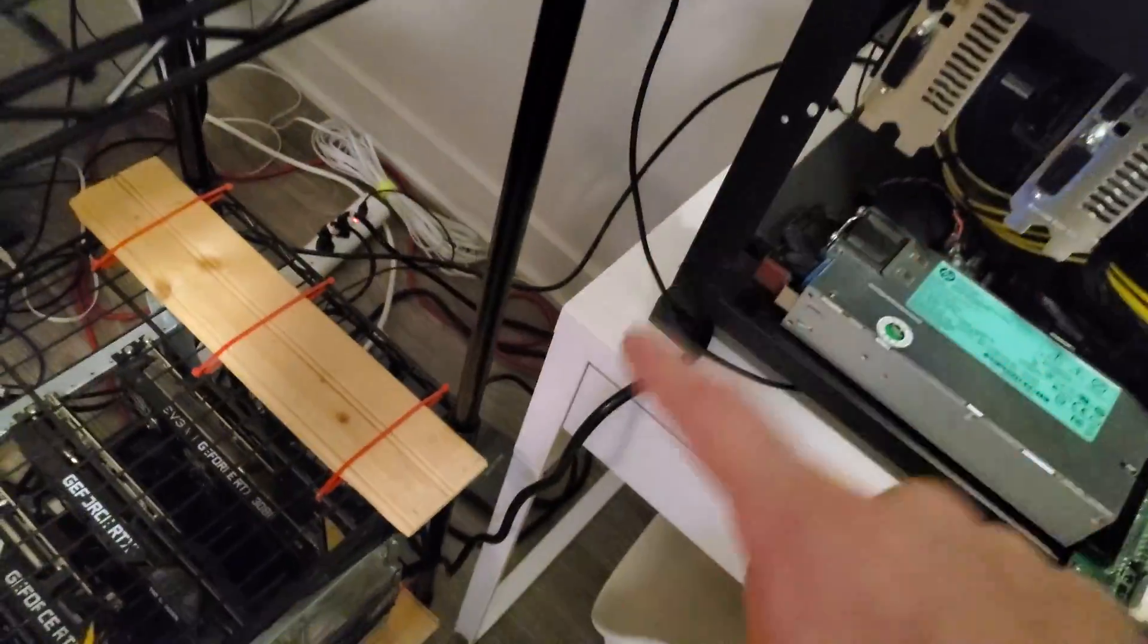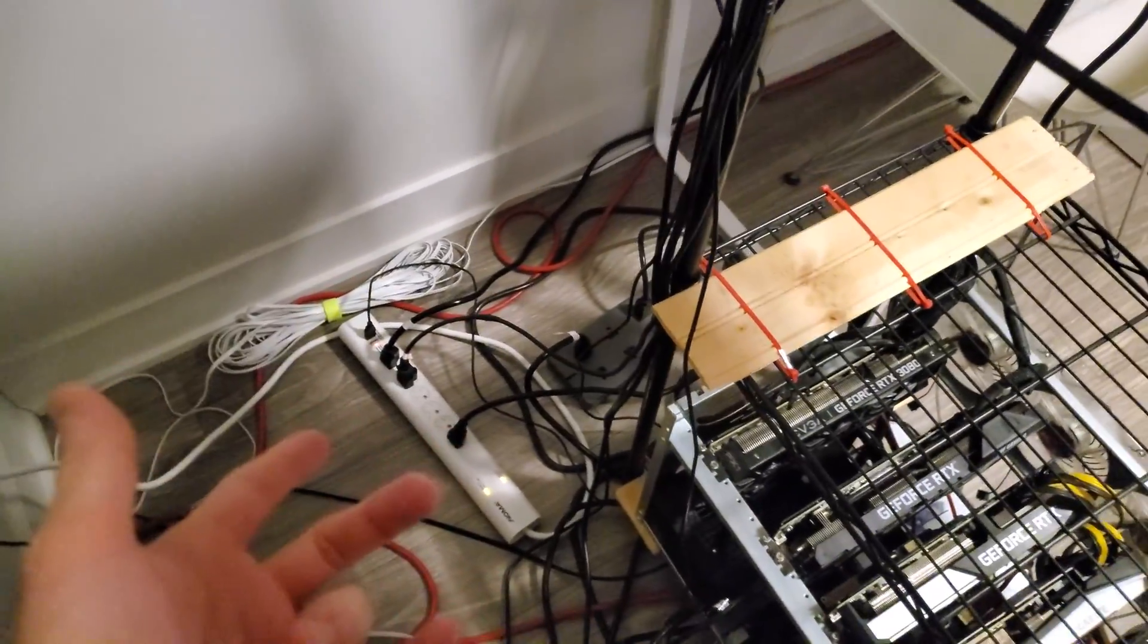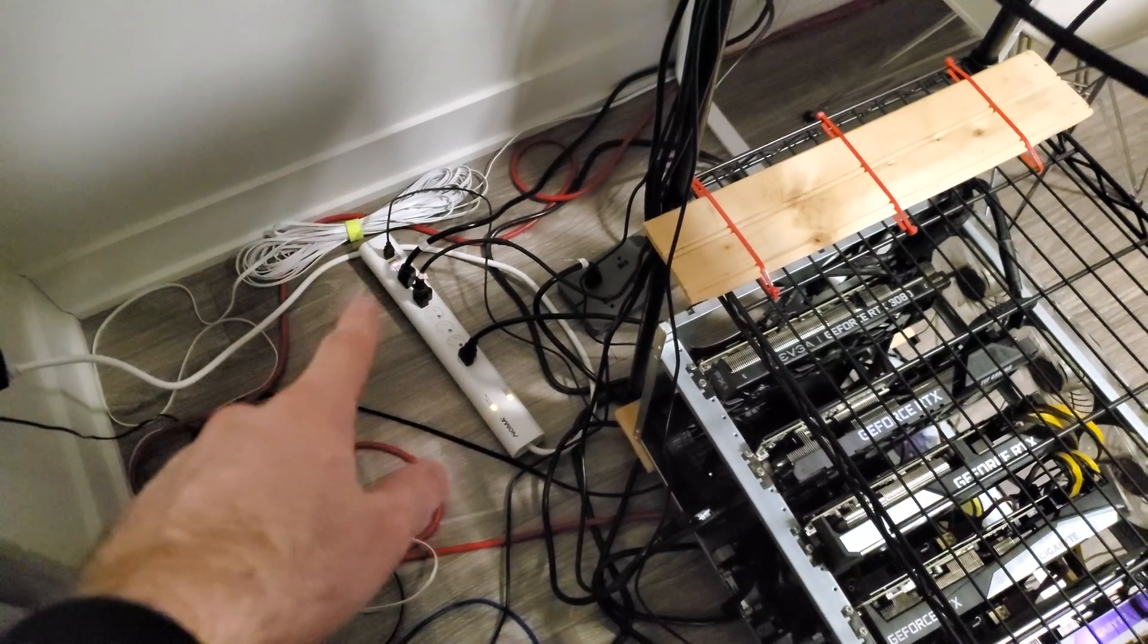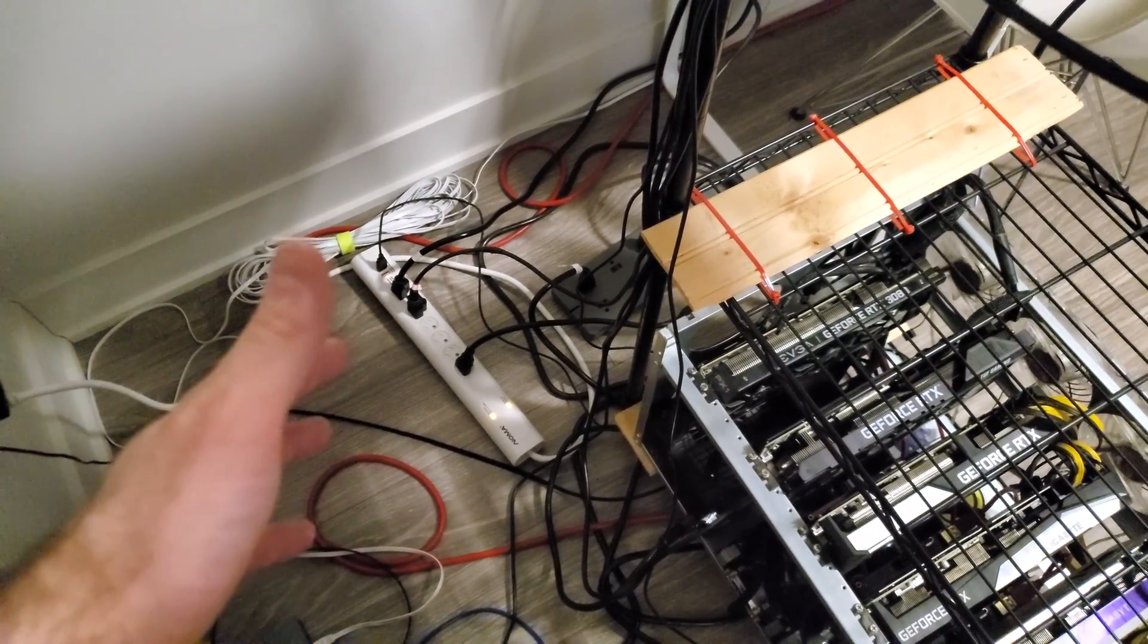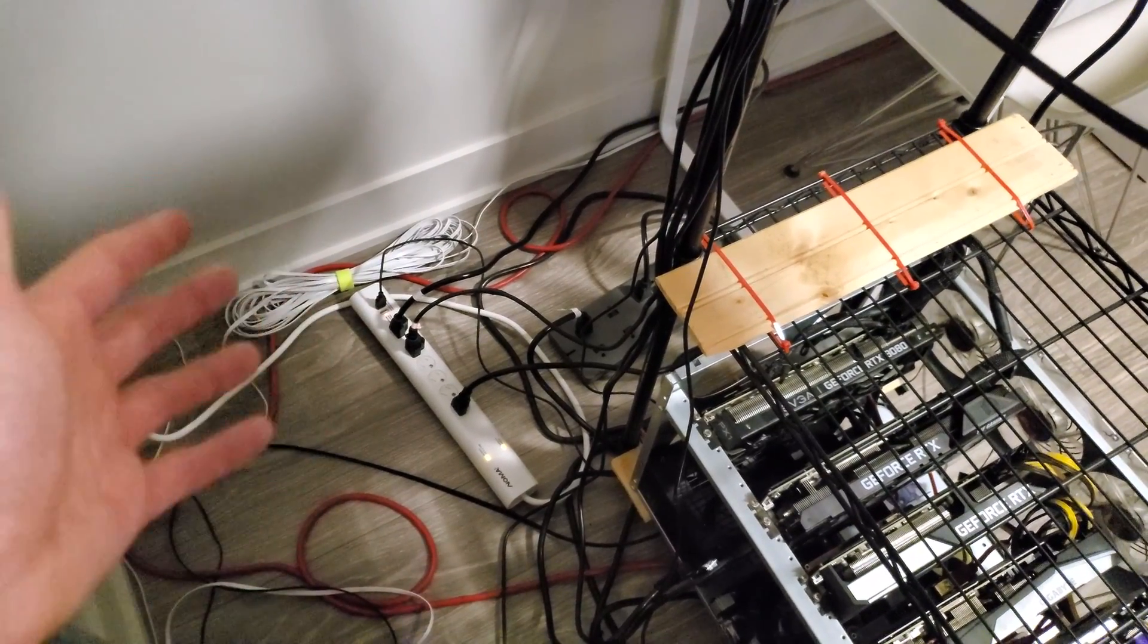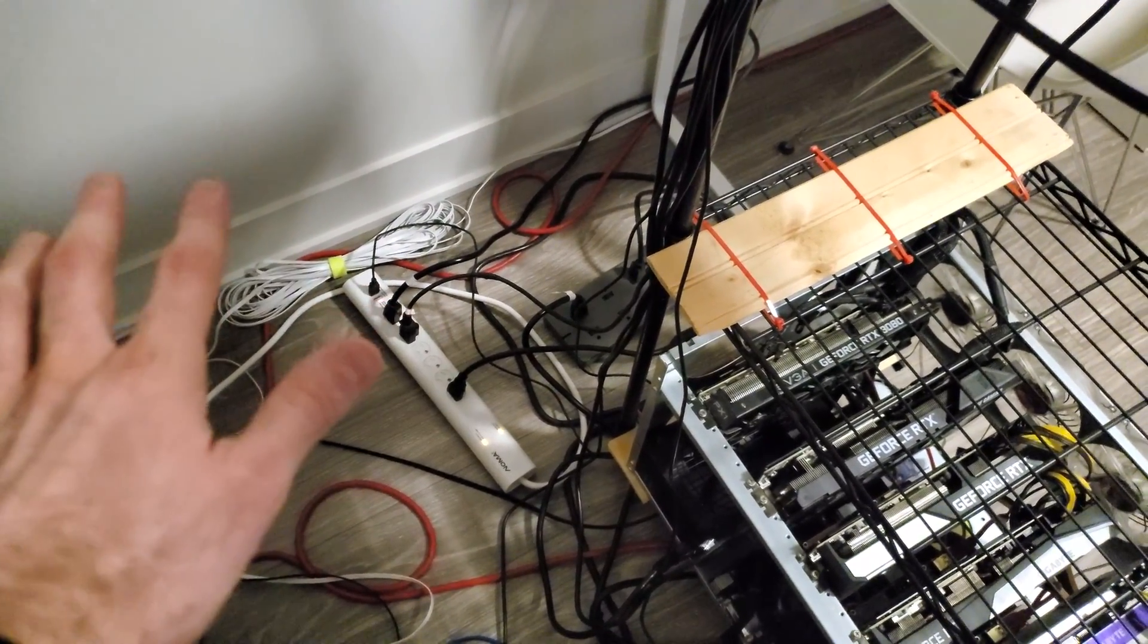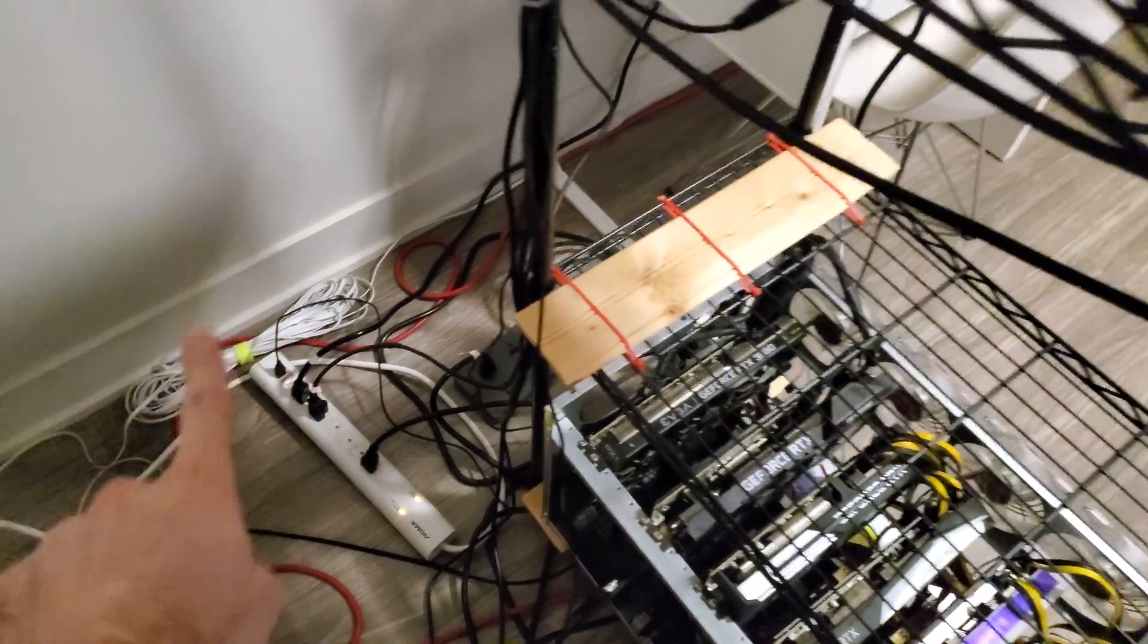Make sure your power bars, if you are using any on especially 120 volt, if you're on 240, you should be using PDUs. On 120, make sure your power bars are rated for at least 15 amps and minimum can run the whole circuit. So 1,500 watts if you're doing the 80% rule more or less. It's better safe than sorry.